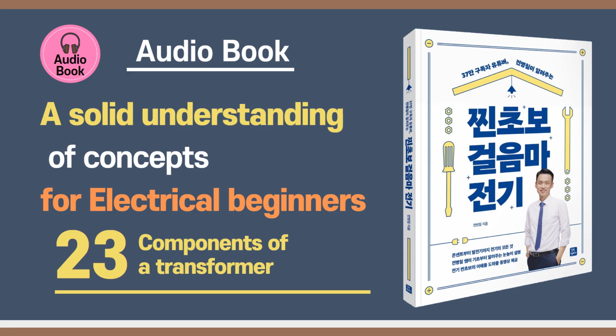Absolutely. The windings are the conductors handling the flow of electricity, and they're almost always made of copper wire. Why copper? Simple. It's a fantastic electrical conductor. Lets electricity flow really easily with very little resistance. Less resistance means less energy wasted as heat just from the current flowing through the wire itself. Maximizes efficiency. Now, for smaller transformers, like our little travel converter, plain old round copper wire is pretty common. Works just fine. Like the wire inside a lamp cord just wound many times.